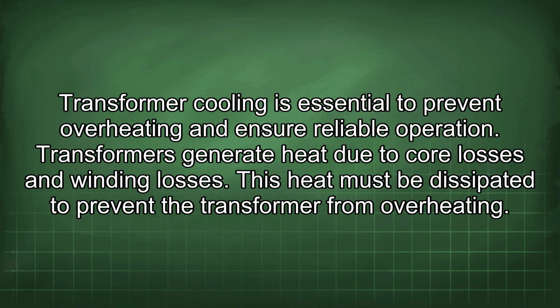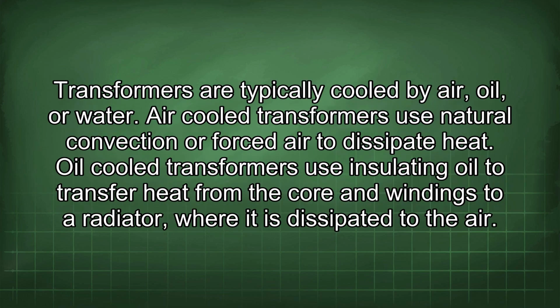Transformer cooling is essential to prevent overheating and ensure reliable operation. Transformers generate heat due to core losses and winding losses. This heat must be dissipated to prevent the transformer from overheating. Transformers are typically cooled by air, oil, or water. Air-cooled transformers use natural convection or forced air to dissipate heat.